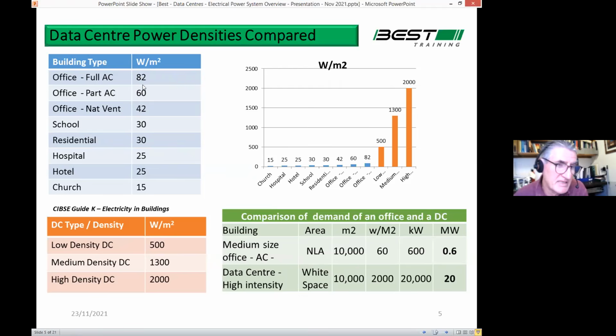It'd be more typically around 60 now, because air conditioning processes have changed and they've gone for natural ventilation a lot. So a typical office might be taking 60 watts per square meter of demand, down to something like a hotel might be only 25, or a church or a bank, a small building like that, 15 watts. There's hardly any load in it at all.